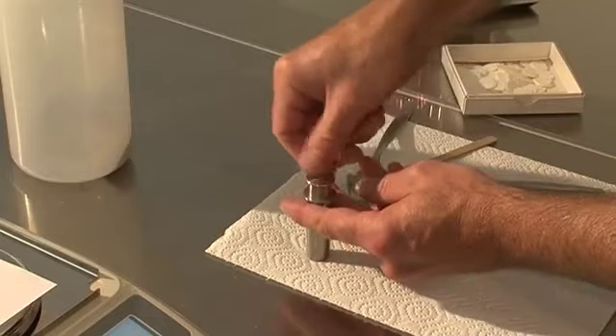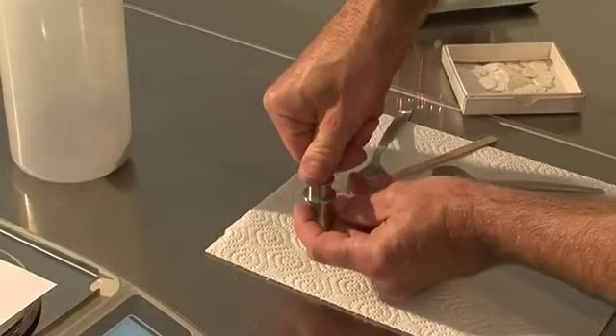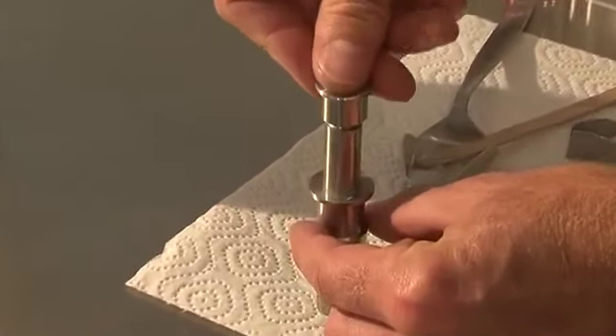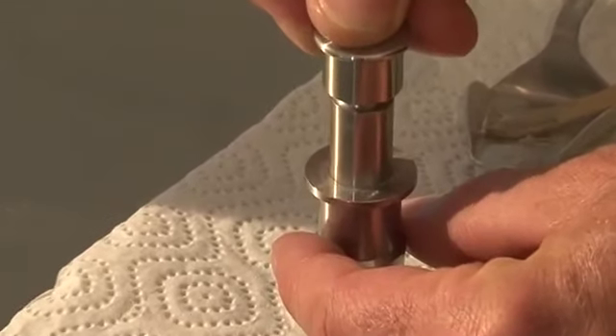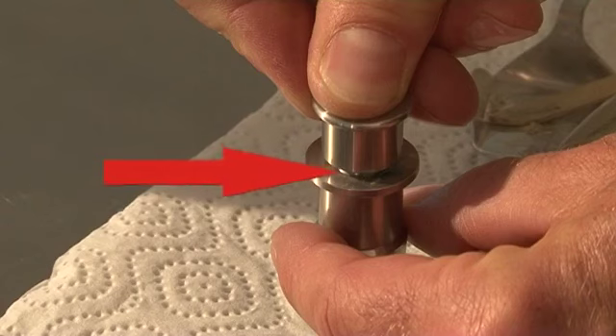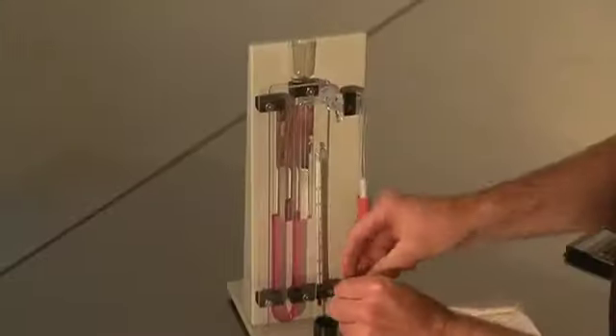Caution: if the plunger falls through without any pressure, the sample weight is incorrect. The porosity must be altered until the compaction condition is correct. The same applies to a plunger which can't be completely pressed down to the stop. Repeat the test with altered porosity and a new sample until the conditions are correct.